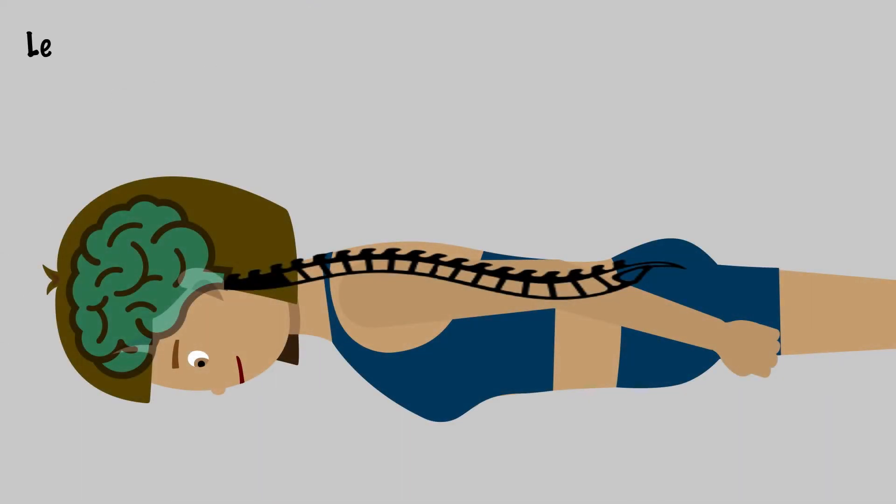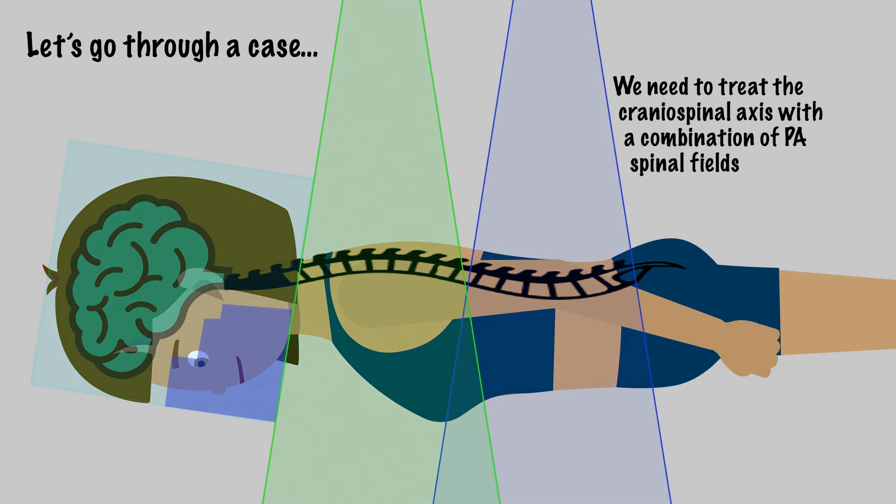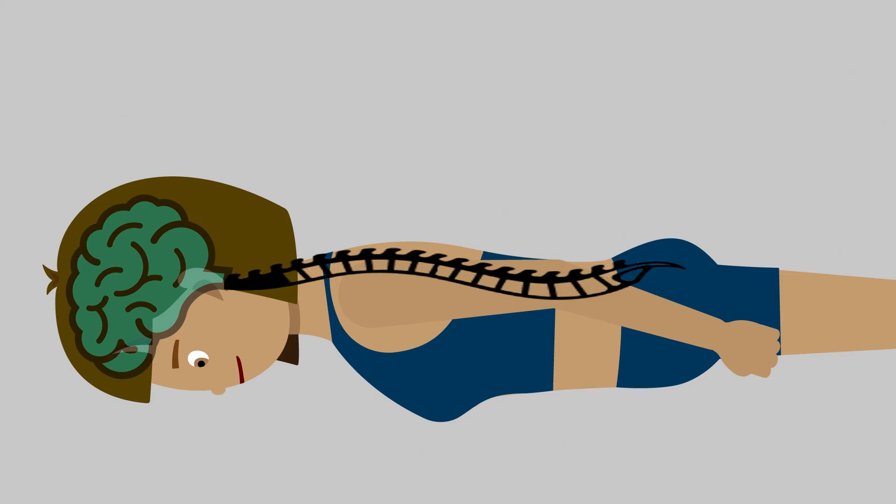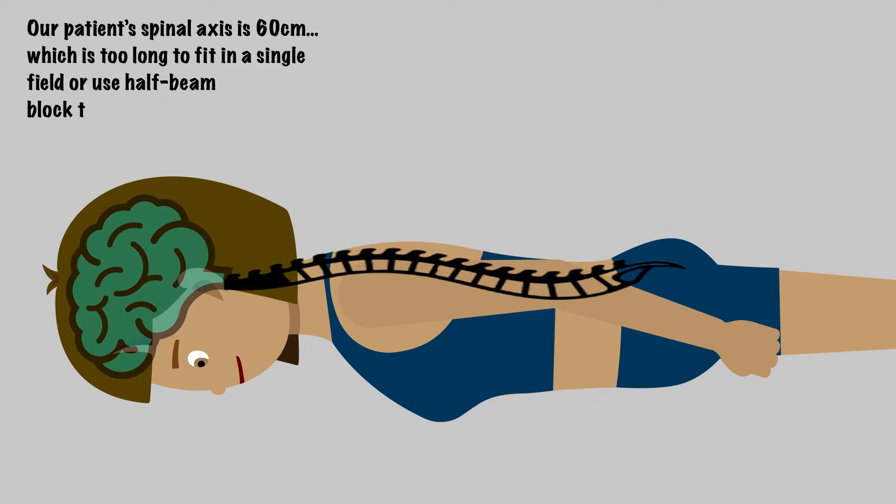Now we will go through an example of how field matching may come up in practice with a craniospinal irradiation case. Here, the goal is to treat the whole craniospinal axis of the patient, which is accomplished with a combination of PA spinal fields set up with SSD, and two opposed lateral whole brain fields set up SAD. We will start with the spine treatment. For this patient, the spinal axis measures 60 cm, which is too long to fit in a single field or to use a half-beam blocked technique.